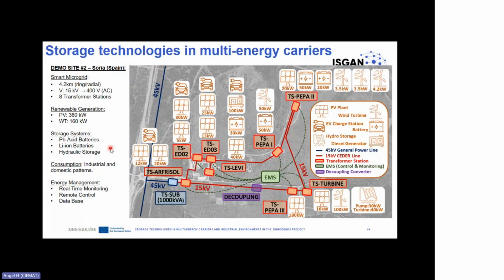Here we have a very huge microgrid, more than 4 kilometers in length. We can operate it in radial and ring modes. It's connected to the general supply grid through the main transformer that converts 45 kilovolts into 15 kilovolts, and after that, through our 8 transformer stations, we convert it into 400 volts low voltage. We have several distribution systems along the area.